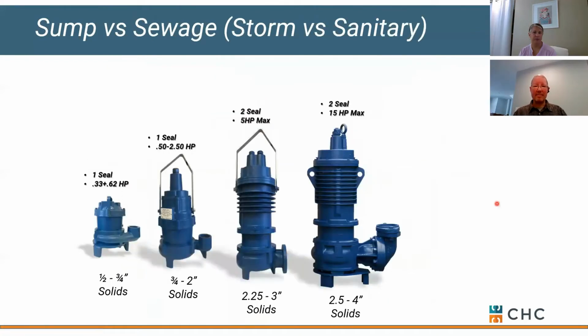Okay. Sump versus sewage, storm versus sanitary. I think where I'm going here is the fact that we might have some single seal pumps that are designed for 1/2 through 2-inch solids. But anytime we're dealing with sanitary or sewage, we usually want the ability to pass 2 1/4 or larger on solid size. So most commercial sewage pumps are designed for larger solids. And you'll see that their housing is very tall, allowing them to do that. It's also a 2-seal setup.